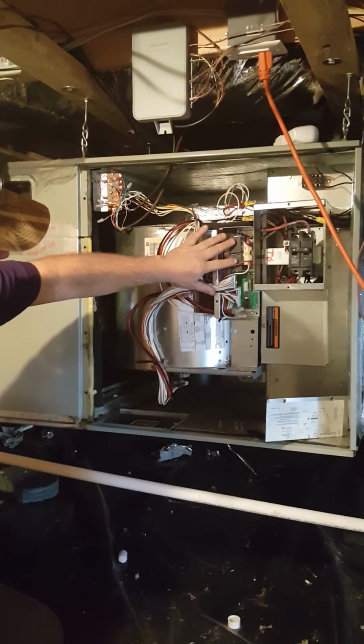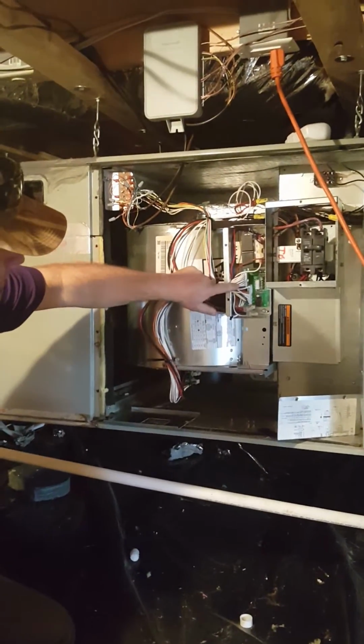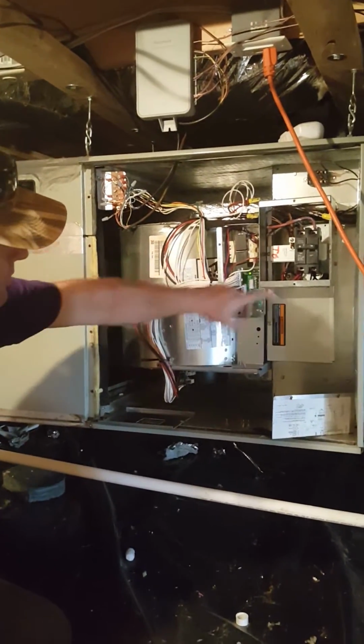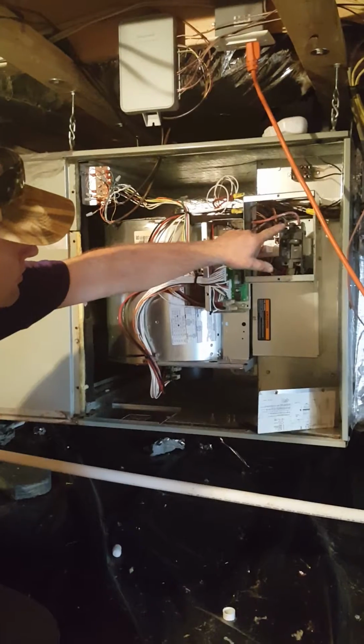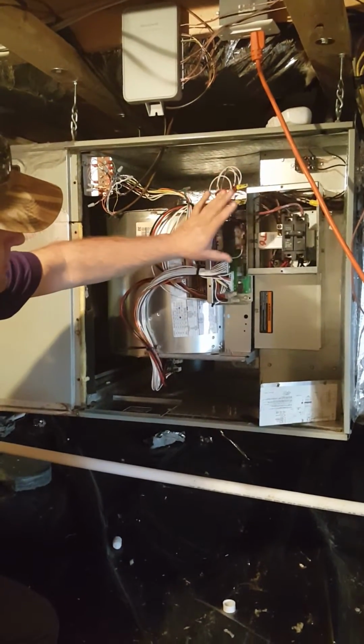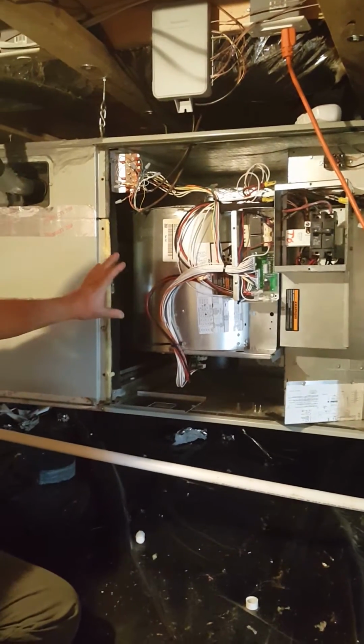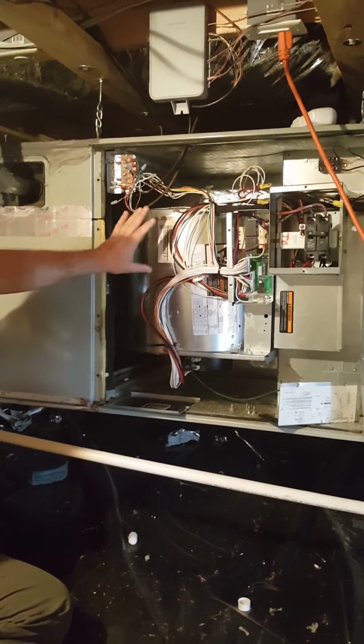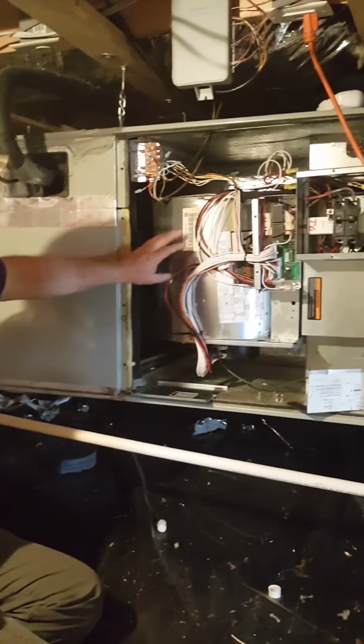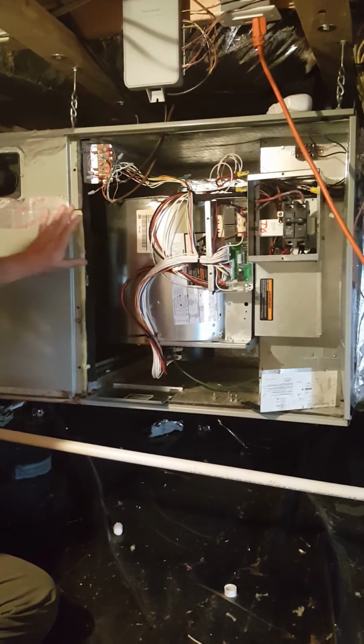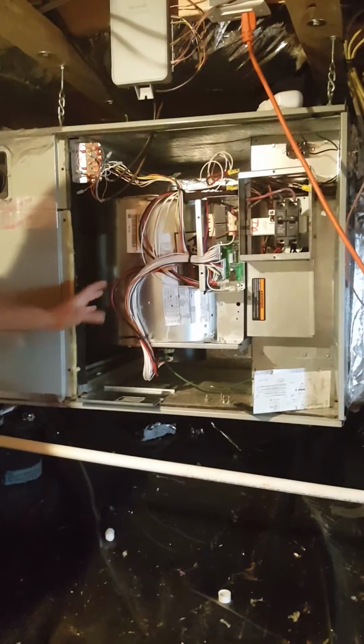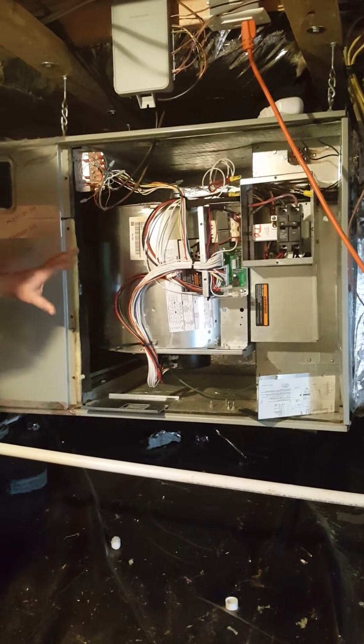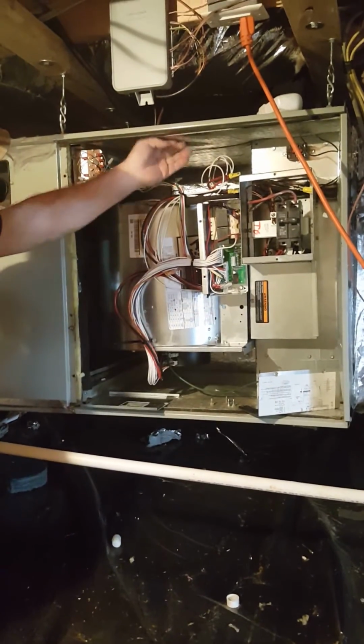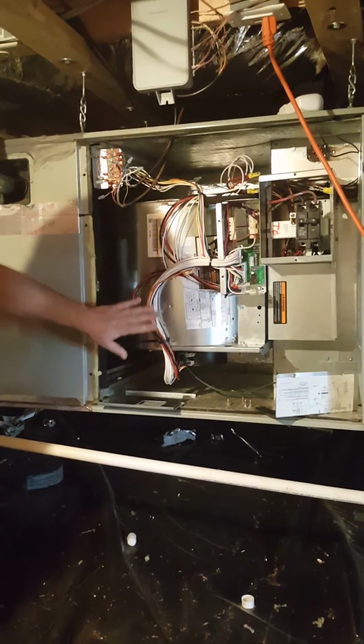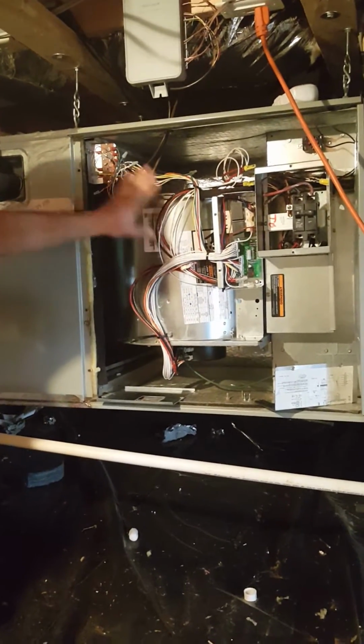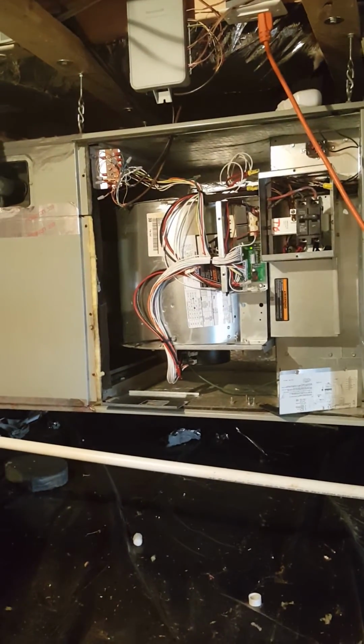Then we're going to check this transformer. We have a control board that controls the motor. We also have the main breaker for the unit. We're going to check the high voltage connections, making sure nothing's getting loose or damaged there. We're also going to check the voltage and the amperage. This unit doesn't have a capacitor on the fan motor, but most do, so we'd also check that capacitor. The other thing we're going to do is make sure there's no mildew that's built up over time on the insulation down here on the bottom or the top. A lot of times you'll see mildew, dirt, and debris built up on this wiring, so we'll clean that off also.